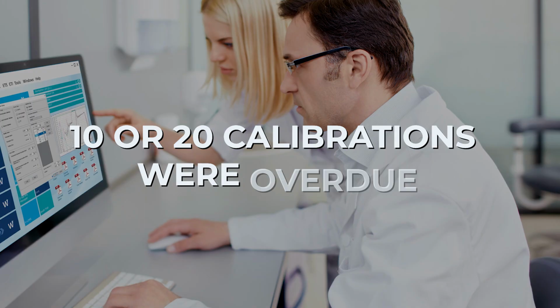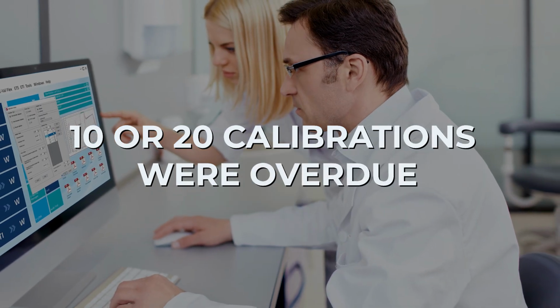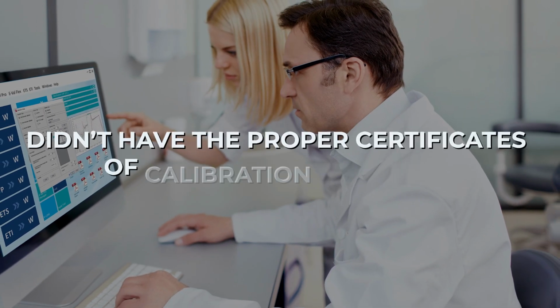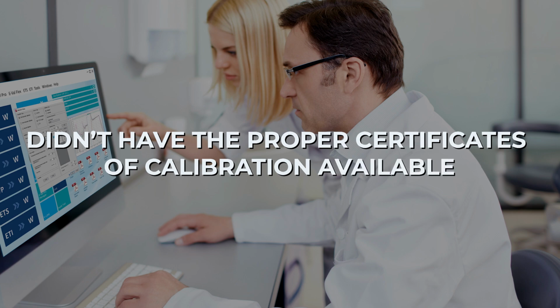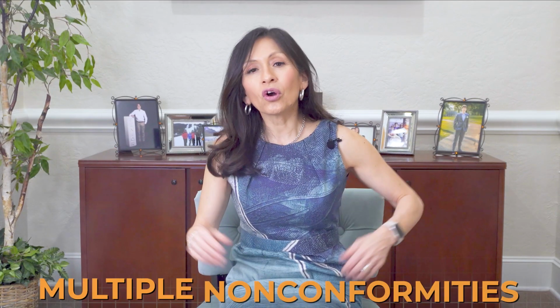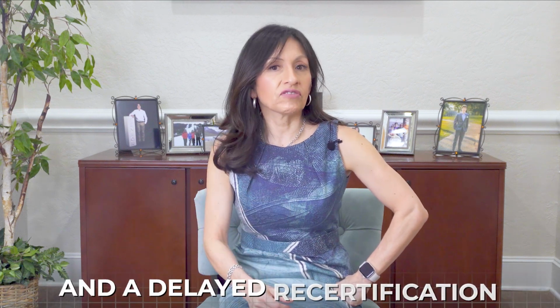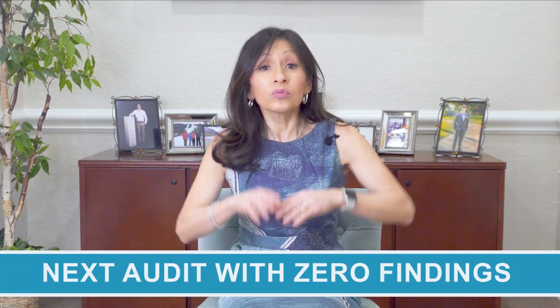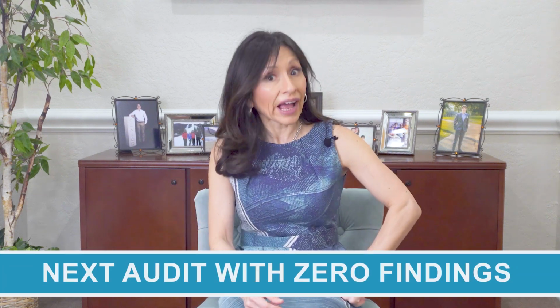No pun intended. One day during their audit, they realized that more than 10 or 20 calibrations were overdue, and another 15 or more didn't have the proper certificates of calibration available. The result, multiple non-conformities and a delayed recertification. After switching to a calibration software, they cleaned up their entire asset list, updated their certificates, and eliminated overdue calibrations, and went through their next audit with zero findings related to calibration.